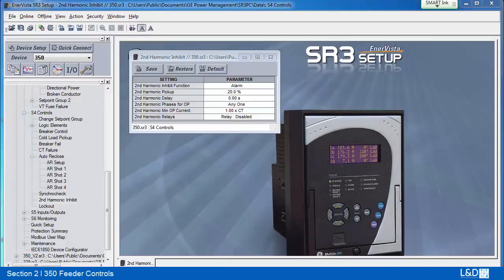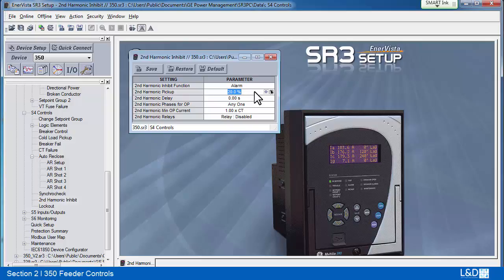Otherwise, the function must check the angle difference by taking into account the breaker closing time setting. The 350 relay can be used for feeder transformer protection. During transformer energization, the inrush current in the phase current may impact some sensitive elements such as neutral directional overcurrent. Therefore, the ratio of the second harmonic to the fundamental magnitude of the current per phase is monitored. When this ratio exceeds the pickup level, an inhibit signal is asserted, which can be used to block such sensitive elements.